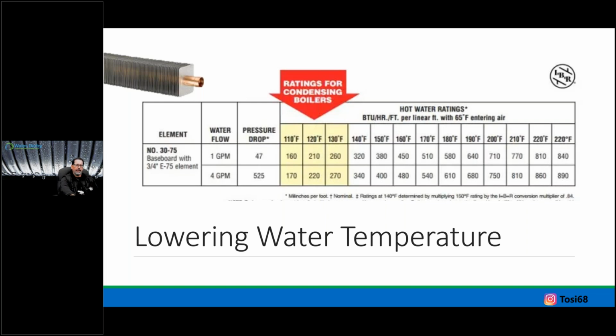Know the differences. Again, I'm doing panel radiators, I'm doing hydrocoils. All these things have ratings of flow versus temperature. So if you look at the chart here, if you live in that 180 world on a 1 GPM flow rate, the top there, it's saying 580 BTUs per lineal foot, not copper tube, of the actual fins. Well, if I had a room 10 foot, that's how many BTUs? 5,800 BTUs. Well, the room only needs 2,000.